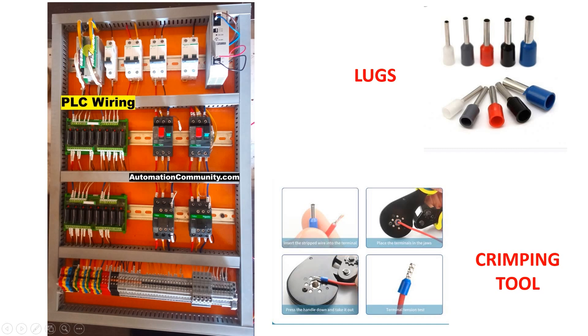Similarly, for outputs the 24V supply goes to the common of the outputs. That means in common we have 24V, and if Y0 or Y1 is on then through the white cable it will have power. You can see I have given 0V to this connector — here there are links, and by using these links you can give 0V to other relays. In this way we will turn on outputs like solenoid valves, contactors, or indicating lights.